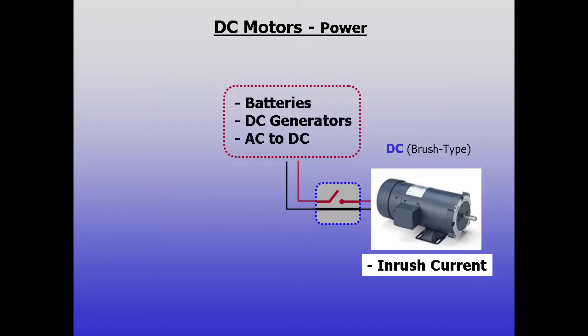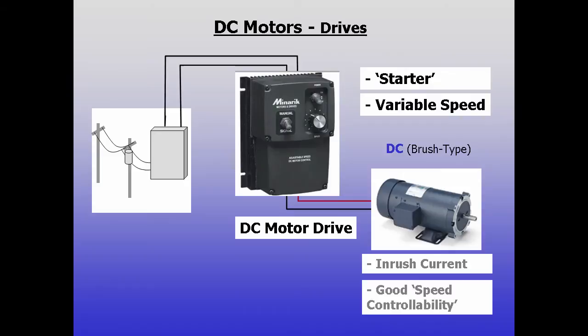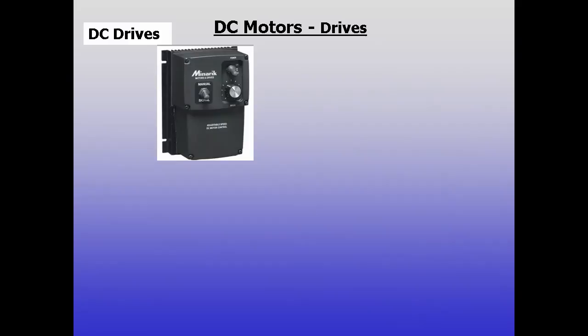DC motors also draw high amperage on startup, so the supply must be adequate and at a minimum a switch must be used that can handle the amperage. Because of their ease of controllability, DC motors are usually used with motor drives. DC drives can act as a starting switch and also provide variable speed of the motor.